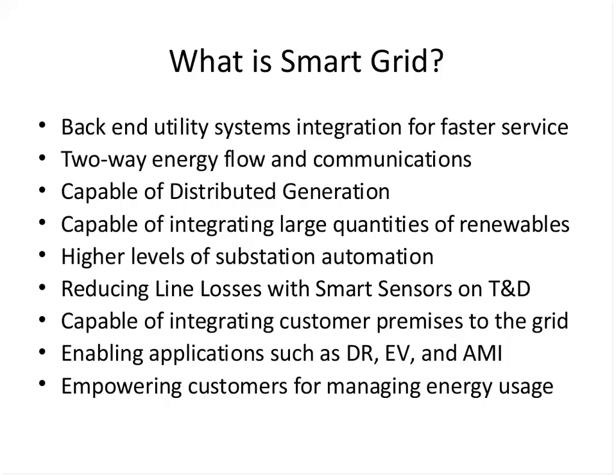When they're brought back, they can be put into what's called a Common Information Model, or CIM. There's an IEC standard for it: for distribution it's 61968, for transmission it's 61970. Libraries are being developed to document all the granular attributes of the grid, and this is key in doing back-end integration with the CIM model.